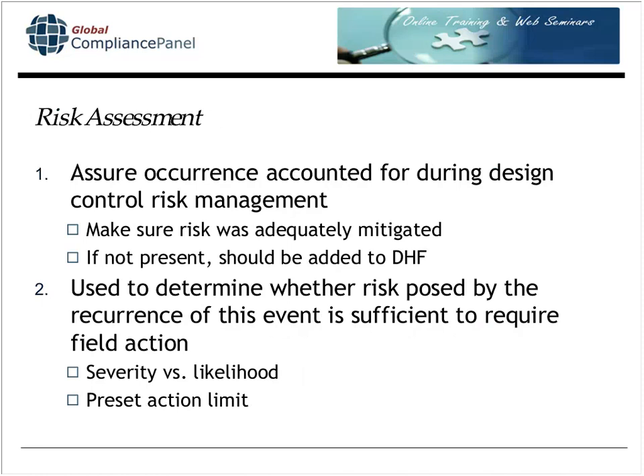Something that's often overlooked when it comes to complaint handling is the concept of applying risk assessment to complaint handling. When it comes to risk assessment of a particular complaint allegation, you want to make sure that the occurrence of that allegation has been previously accounted for during your design control risk management. When you perform your risk assessment early on, you state severity, likelihood, and detection for each possible occurrence. If you have a particular occurrence, tip falling off, for example, that was not accounted for during design control risk management up front, it's your company's responsibility to modify that risk assessment.